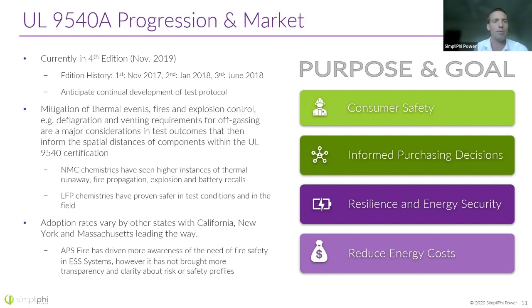SimpliPhi power batteries might be the most tested batteries in operation in the US. We go through all of this safety testing, because safety is a very important part of our business model—it's important to us that our customers have safe options to back up power with. That's one of the principal reasons we use LFP batteries: longer lifetimes, but also much greater safety compared to other chemistries. Lithium ferrophosphate batteries are safer, while NMC batteries are typically the ones you see in fires.